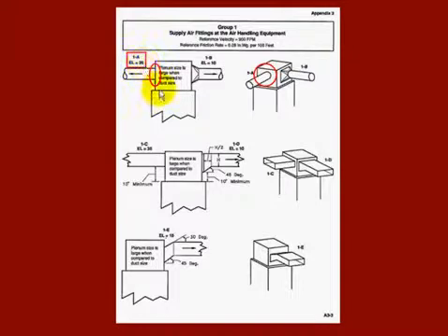That means turning air out of this plenum into this collar is equivalent to 35 feet of straight duct. The pressure drop is equivalent to 35 feet of straight duct. Pretty easy thing to measure. You measure the pressure drop through there with accurate instruments, then you set up a blower with straight duct on it, and you go out away from the blower until you hit a point where you have the same pressure drop, and you say, oh, look at this, I'm 35 feet away from the blower. Very simple thing to do, fairly accurate.